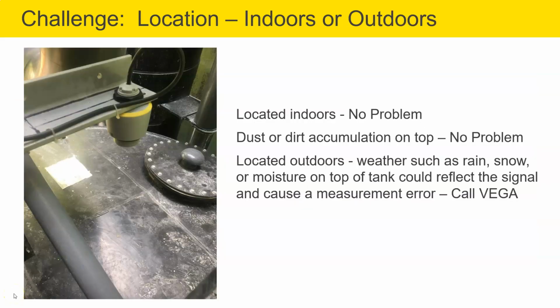Another challenge is where the tanks are located. Are they indoors or outside? When we mount a radar above the tank, we need to ensure that the tank is located inside so that weather such as rain, snow, or moisture on top of the tank doesn't reflect the signal and cause a measurement error. We really aren't concerned about dust or dirt accumulation on top of the vessel, because this typically won't interfere with the radar signal.